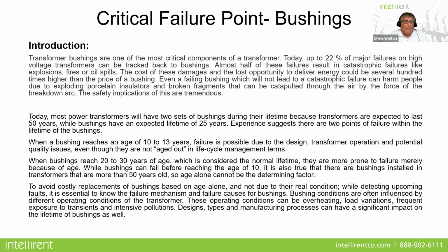So today, most of your power transformers will have at least two sets of bushings during their lifetime, and sometimes three, depending on the condition. We see transformers now, if they're well taken care of and not overloaded, lasting 50, 60 years, sometimes even longer. And at that point, under normal conditions, your bushings will have a life expectancy of about 25 years.